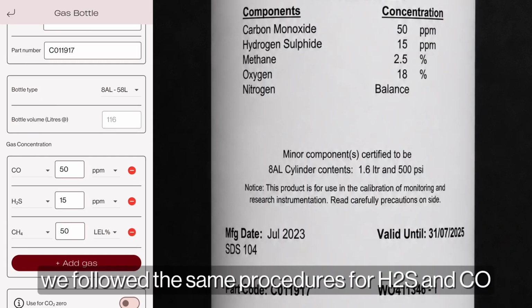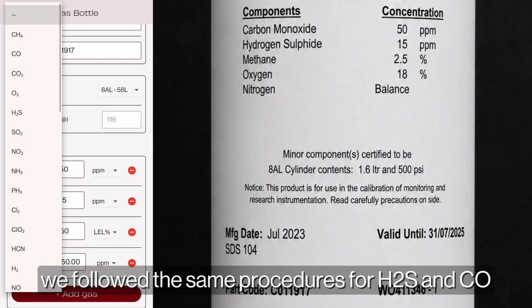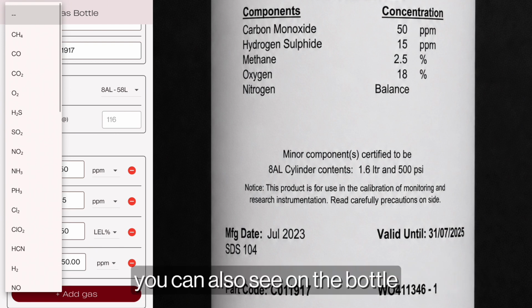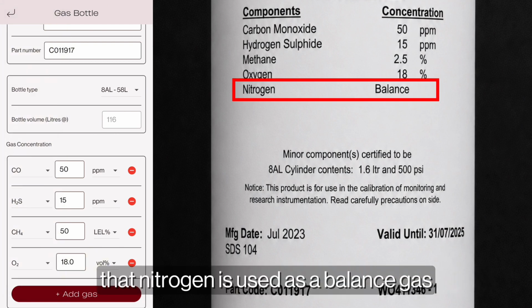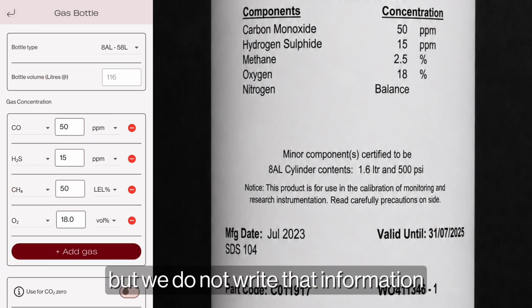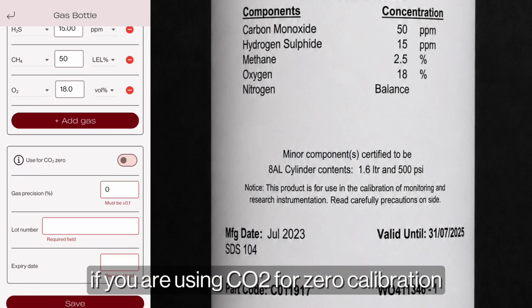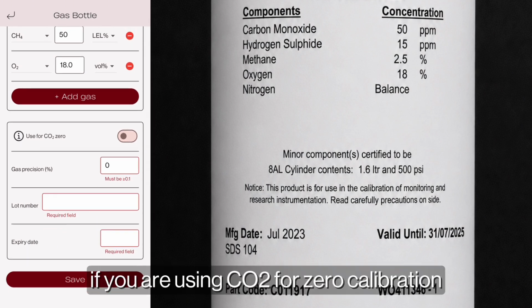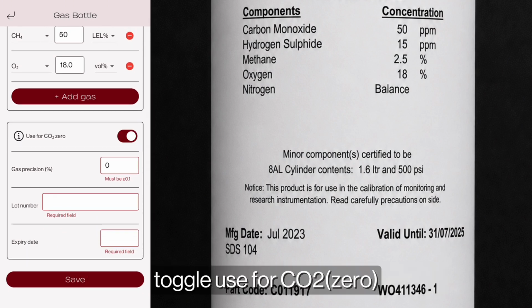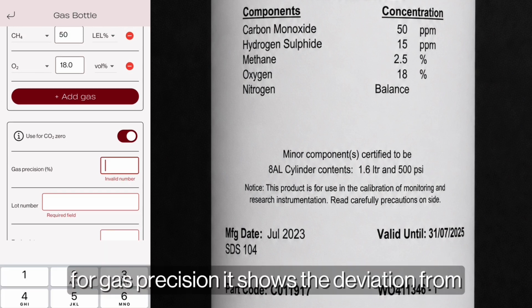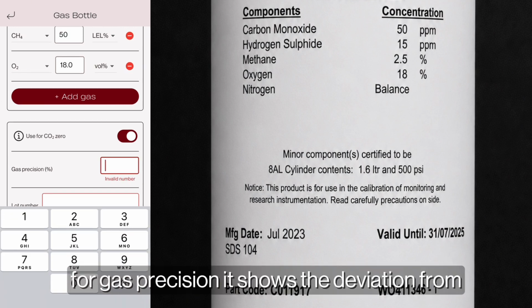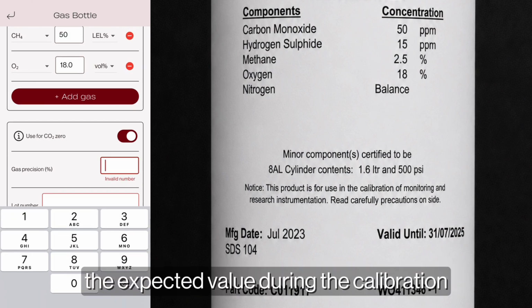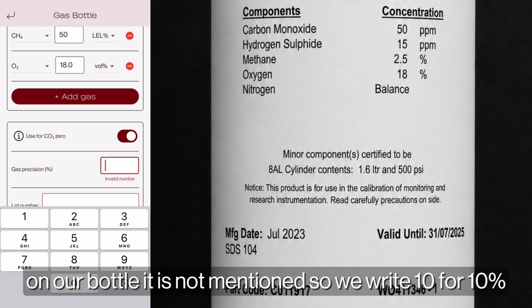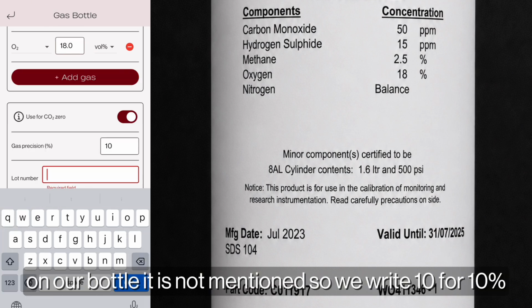For oxygen, we followed the same procedure as for H2S and CO. You can also see on the bottle that nitrogen is used as a balance gas, but we do not write that information. If you were using CO2 for zero calibration, toggle Use for CO2 zero. For gas precision, it shows the deviation from the expected value during the calibration. On our bottle, it is not mentioned, so we write 10 for 10%.